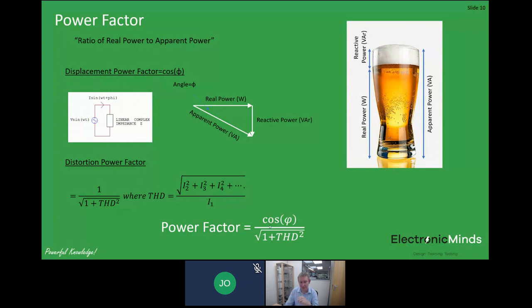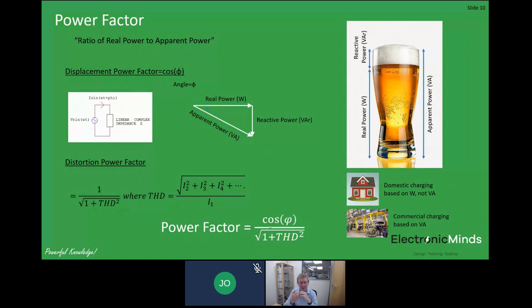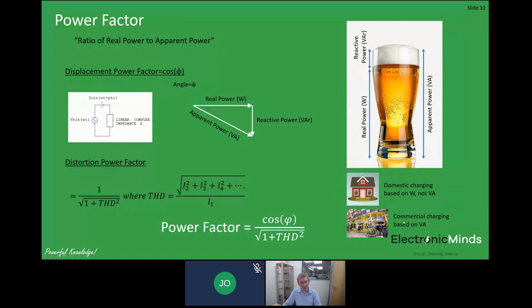The interesting thing is that in the UK at home you're charged based on real power — your energy meter measures real power use. You don't get charged based on the VA power you impose on the grid. However, for commercial applications where power levels are much higher, the impact of poor power factor is quite severe — commercial customers get billed based on the apparent power of their system. So there's a lot of drive to manage your VA rating if you've got commercial premises or a big factory, otherwise you get penalized financially.